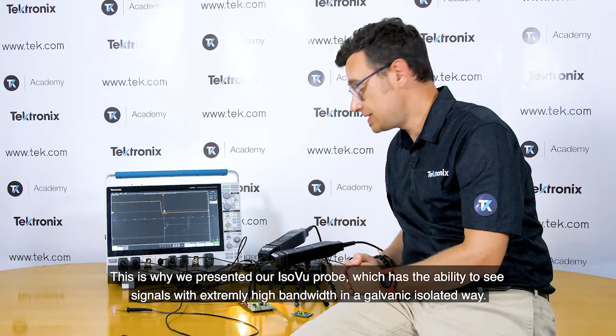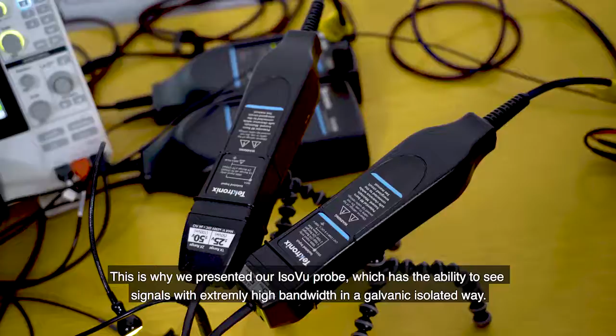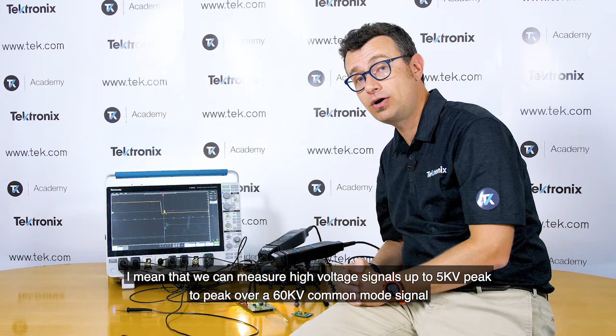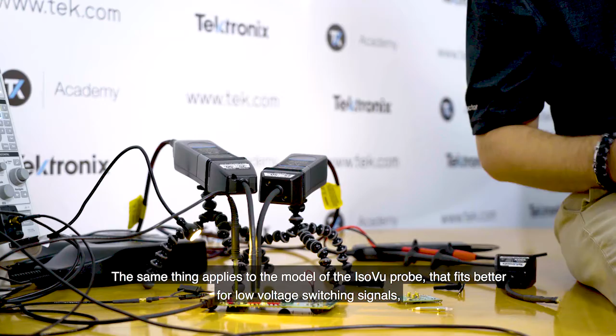But by doing this, you also need to respect several other constraints, like for instance the common mode rejection ratio. This is why we presented our IsoVu probe, which has the ability to see signals with extremely high bandwidth in a galvanically isolated way. I mean that we can measure high voltage signals up to 5 kilovolts peak to peak over a 60 kilovolt common mode signal with 800 megahertz of bandwidth. And the common mode rejection ratio doesn't degrade too much with frequency, protecting the accuracy of your measurements. The same applies to the model of the IsoVu probe that fits better for low voltage switching signals, especially when you need to probe and measure the gate voltage, for instance. In this case, we have the possibility to have even 1 gigahertz of bandwidth.